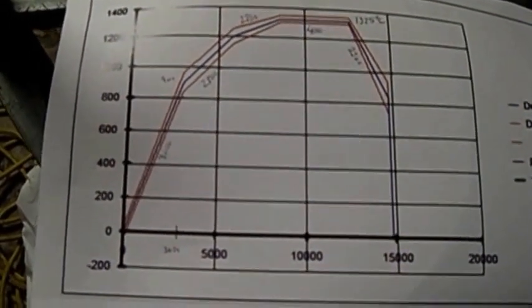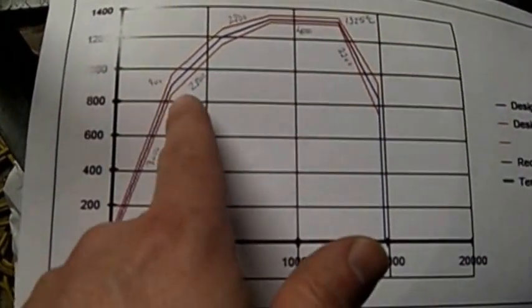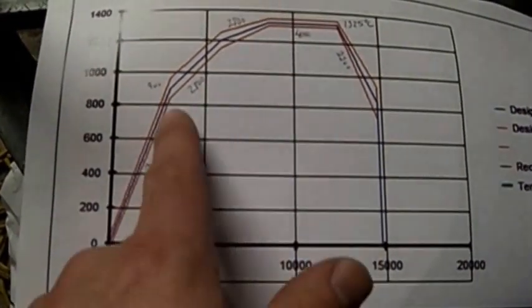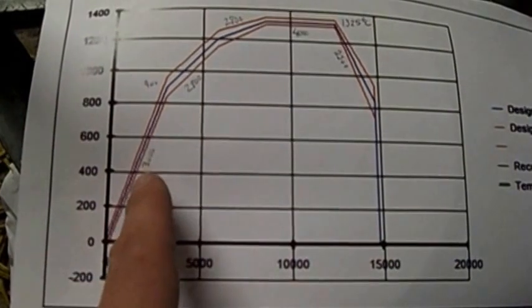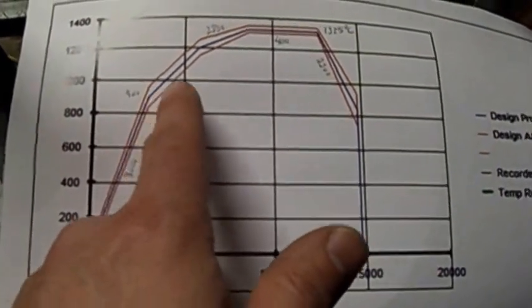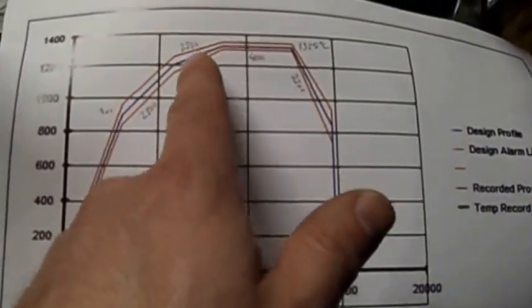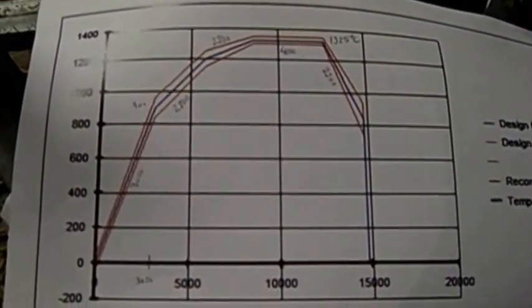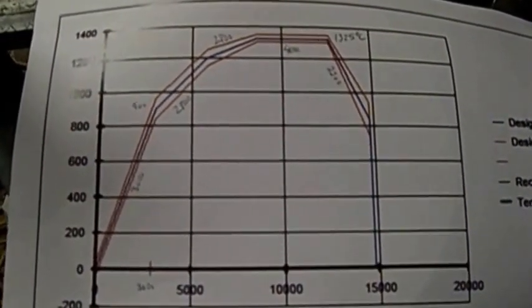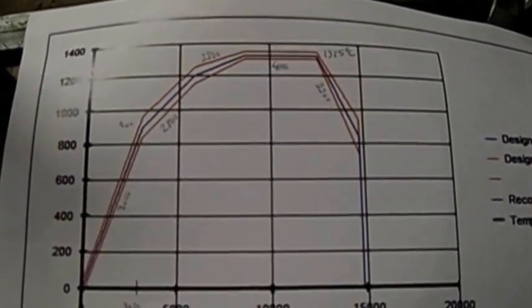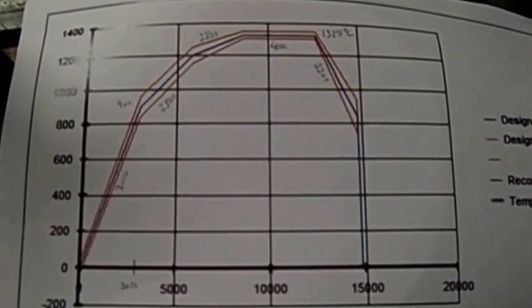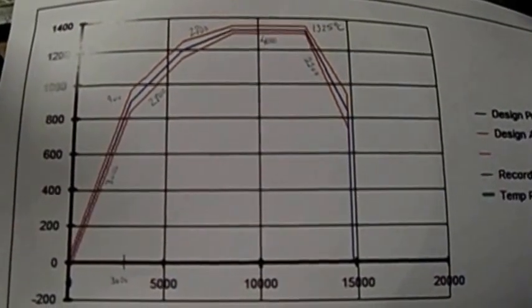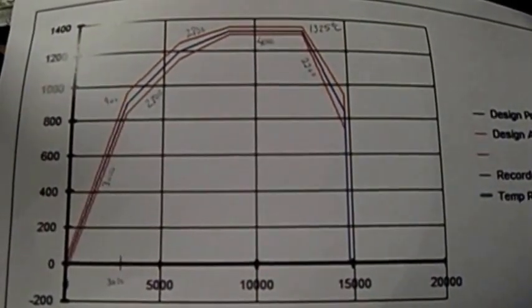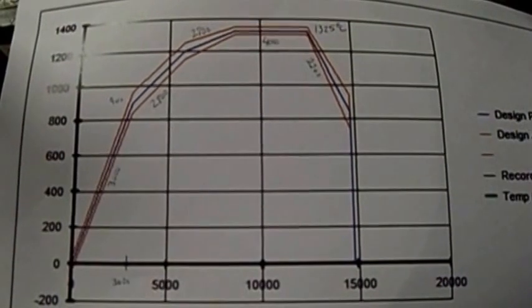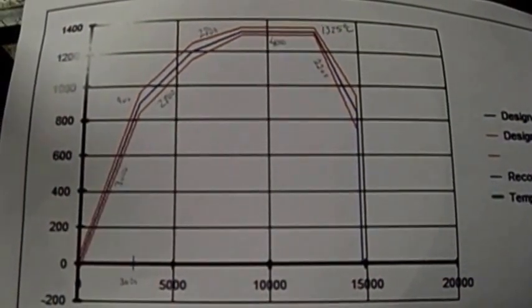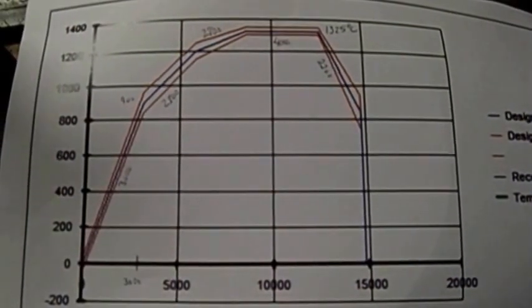Here's the profile. We ramp up fairly quickly. This is material that's thermal shock resistant, so we don't have to worry too much about the ramp up. Then we taper off as we get hotter, just to keep the gas flow approximately equal throughout the firing. We do about an hour hold at 1325, followed by a cool down, and then the gas controller will shut off around 825C, which is a safe limit for the stainless steel burners.